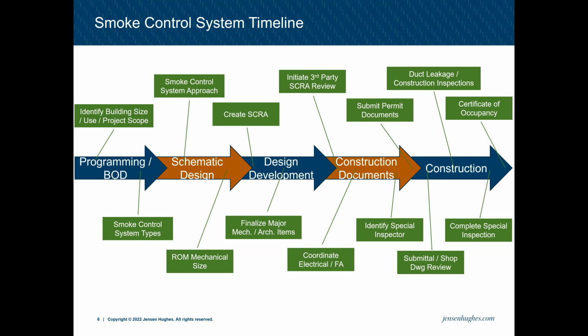Smoke control systems are typically controlled by the fire alarm system as much as possible, and starting to figure out exactly where that's going, the protection of the circuits, and more of the minutia that is involved with smoke control happens in construction documents. Smoke control is a very complex system, so it does require a special inspector. And then near the end of construction documents, or sometimes we're seeing it more and more early, identifying who that special inspector is and getting them on board early on in the project also does help. With the end of construction documents, that's when you'll submit your permit documents, which should have the rational analysis and the special inspectors, and are the documents used for building permit approval.